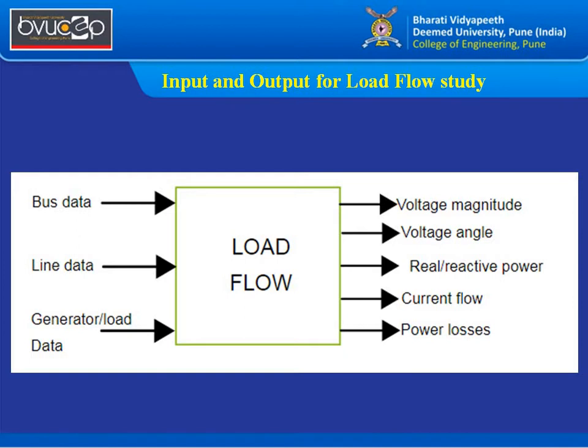Load flow is the heart of the system. Inputs required include bus data (voltage magnitude, voltage angle, real power, reactive power depending on bus type), line data (resistance, reactance), and generator and load data. Outputs obtained after performing load flow include voltage magnitude, voltage angle, real and reactive power, current flow, and power losses — all essential for maintaining the system in stable condition.